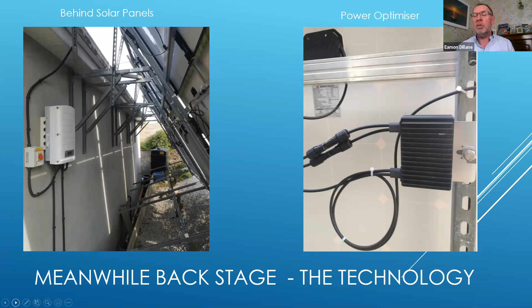And it leaves it very, very safe from an installation perspective. Because if you imagine I've got 16 panels on my system, if I connected 16 of them in series with 40 volts coming out, I'd have 640 volts DC to handle at the end of my lead. However, with this system, I only have 16 volts DC to handle until such time as it's connected to the inverter, and the inverter wakes up the optimizers and it chooses that it wants actually 350 volts DC to be its operating voltage. So I'll just move on now because I want to talk a little bit about optimizers, what they are and why I have them.